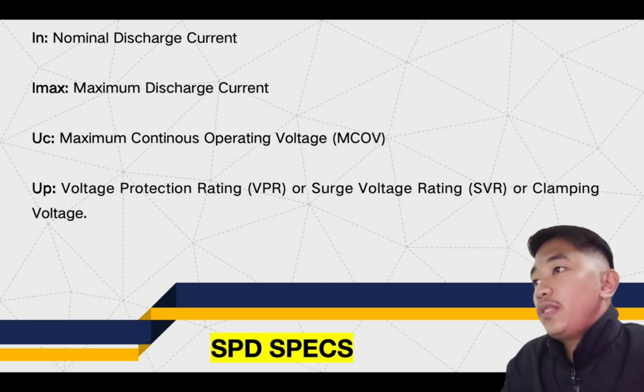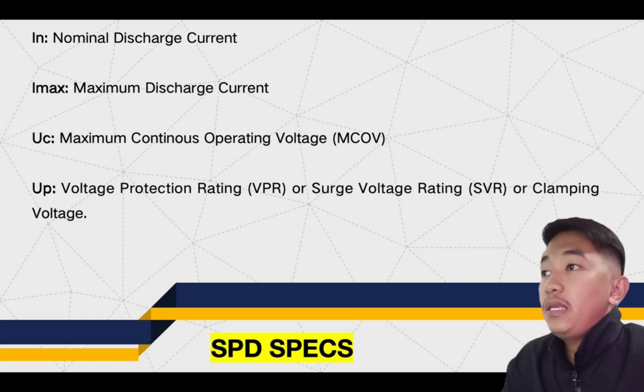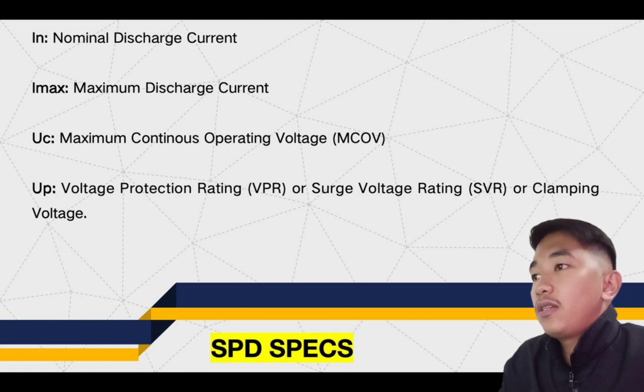Next is the maximum discharge current, Imax. It refers to the highest current a surge protection device can handle during a surge event without being damaged or failing. This rating is important because it defines the ability of the SPD to protect the system during extreme voltage surges, such as those caused by lightning strikes or switching operations. Next is the maximum continuous operating voltage, UC. It is the highest voltage that an SPD can safely handle under normal operating conditions without becoming damaged or degraded.